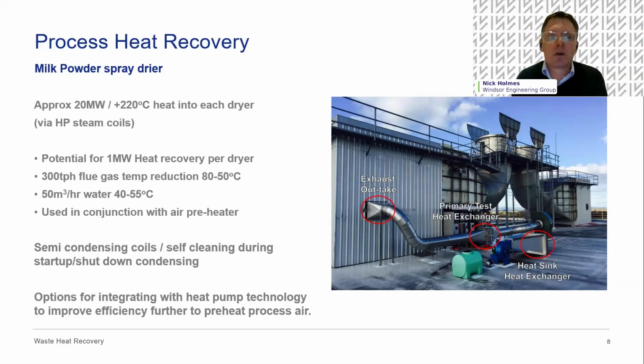But because of the high mass flow, there's still a huge amount of energy recovery that can be pulled from that. So the calculation showed there's a megawatt of heat from each of those dryers out of those stacks that could be recovered, and by putting a water circuit into an air preheater, the air preheater would utilize 55 degree water to preheat the process air, and utilize that 1 megawatt of energy. Obviously a significant project to execute something like that, but we ran a trial in conjunction with one of the universities in New Zealand, and that's what this photograph shows.